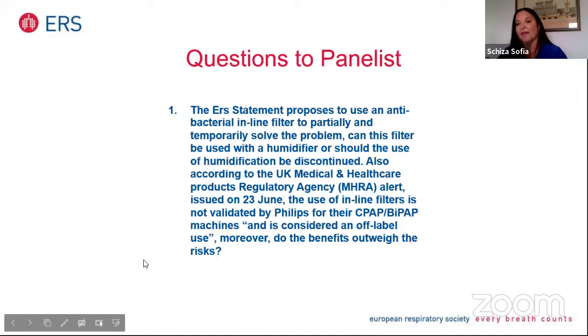We don't know about the volatiles, and we may never know in the near future, but if we closely monitor our patient, and if the patient doesn't exhibit any discomfort or problem with the pressure delivery from the machine, because it's necessary to be titrated previously, then we can continue, and this close monitoring can guide us on the frequency of exchange, if needed, earlier than a month or within a week or so. The problem connected to this is the availability of the filters in the end, and who can cover the filter according to different national agency policies.